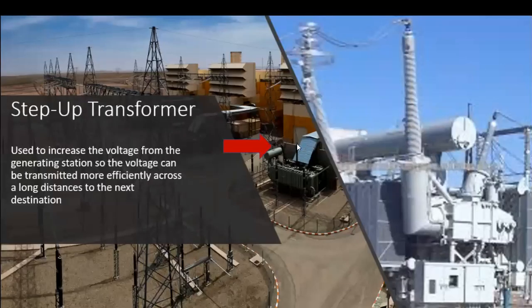Right after it comes out of the generating station, you see this red arrow here, it's going to go into what they call a step-up transformer. We're generating at a lower voltage, not a transmission voltage, to be able to insulate a lot easier, and it's just easier to get out of the generating station, off the generator, to this transformer at those lower voltages. The step-up transformer then is used to increase the voltage from the generating station so the voltage can be transmitted more efficiently across a long distance to the next destination.